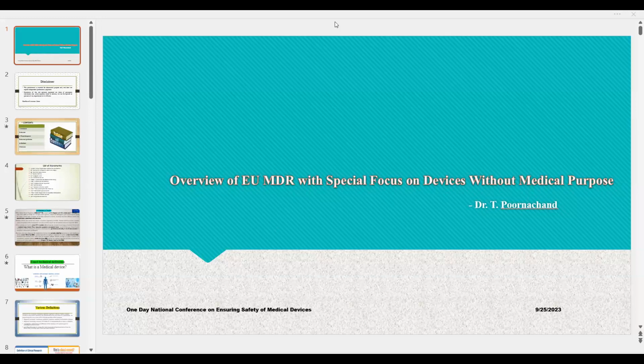Yeah. Thank you, sir. Vishal Tomar wants to know what unique regulatory challenges manufacturers of devices without a medical purpose encounter under the MDR, and how can these challenges be addressed? As I mentioned in one of the last slides of my presentation, the penultimate one, it explains how these devices without a medical purpose impact the manufacturers and the stakeholders. They need to adhere to each and every step that is followed for devices with a medical purpose. The difference is that the severity of the risk is lower with devices without a medical purpose, whereas with a medical purpose it is high. It was also clearly mentioned how they need to go for CE certification, how they go for declaration of conformity, and how they maintain the data on the EUDAMED database as well.